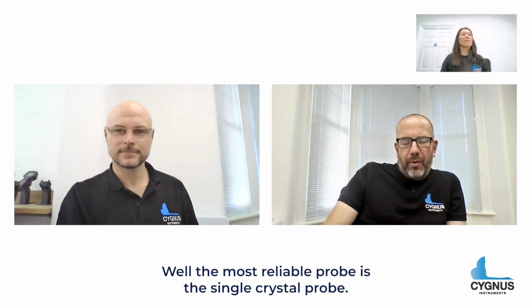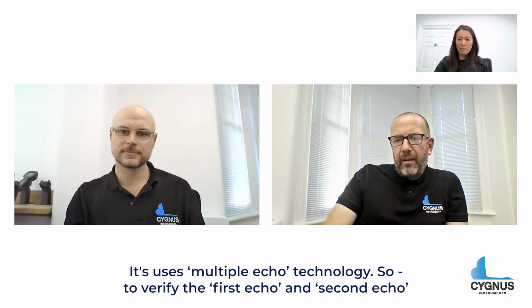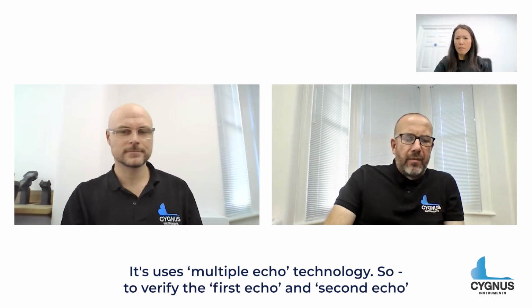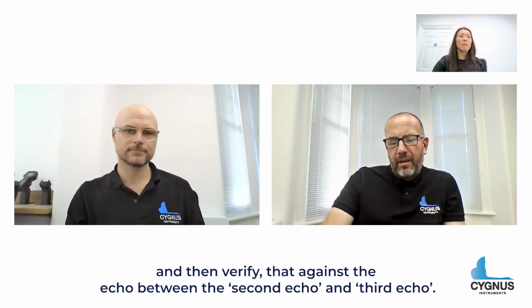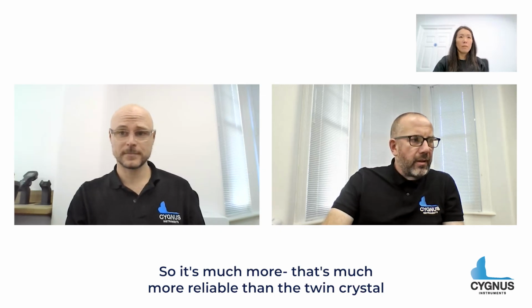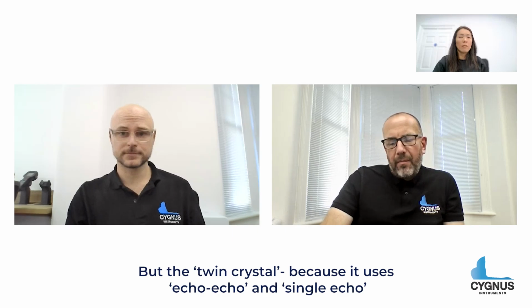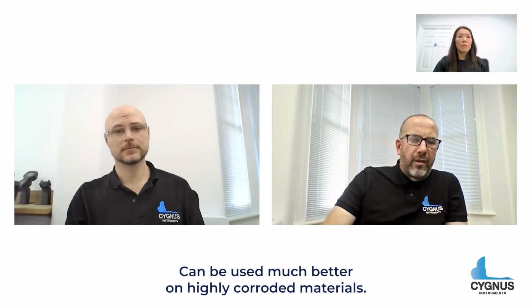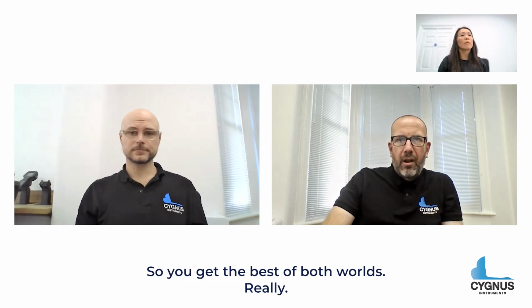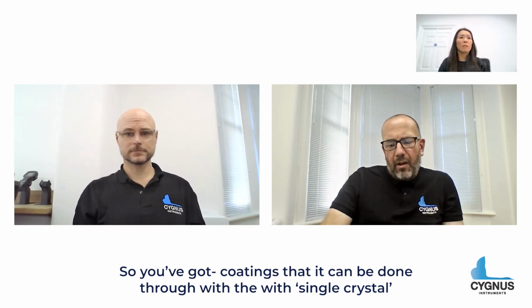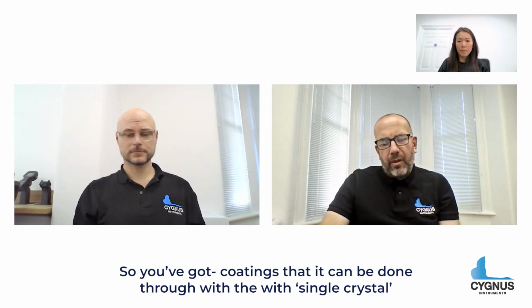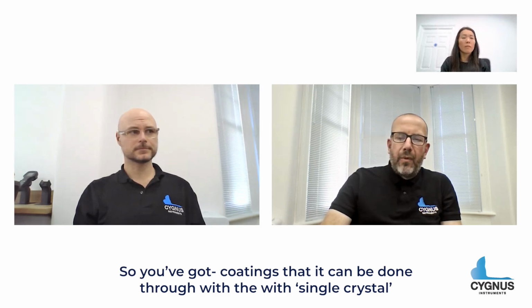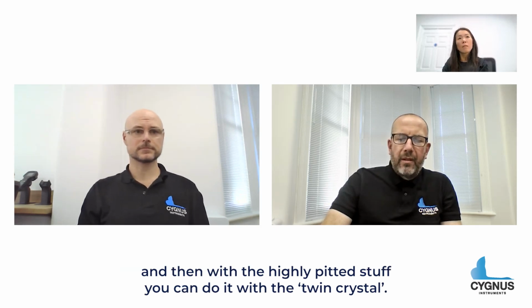Well, the most reliable probe is the single crystal probe. It uses multiple echo technology, so it verifies the first echo and the second echo, and then verifies that against the echo between the second echo and the third echo. That's much more reliable than the twin crystal. But the twin crystal, because it uses single echo, can be used much better on highly corroded materials. So you've got the best of both worlds really. Highly coated surfaces can be measured through with the single crystal, and the highly pitted stuff you can do with the twin crystal.